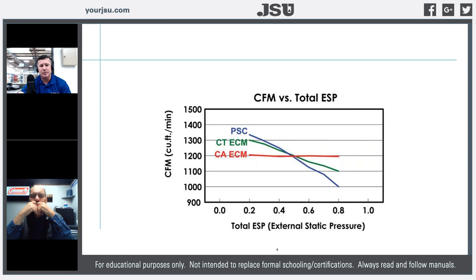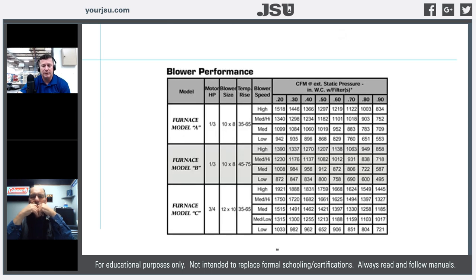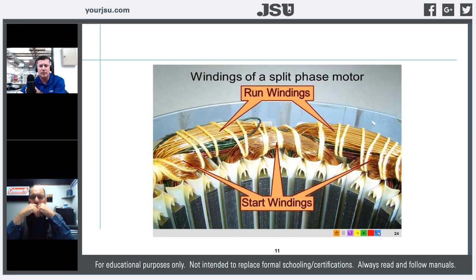Looking at the differences between ECM and PSC motors, we can track static pressure effects and see how much force is being exerted on that capacitor. A lot of problems in the field with capacitor failures are based on PSC motors being used in applications with high external static pressure. As we increase the load on that motor, we increase resistance across the capacitor, increase electron flow, and ultimately increase heat on that capacitor.